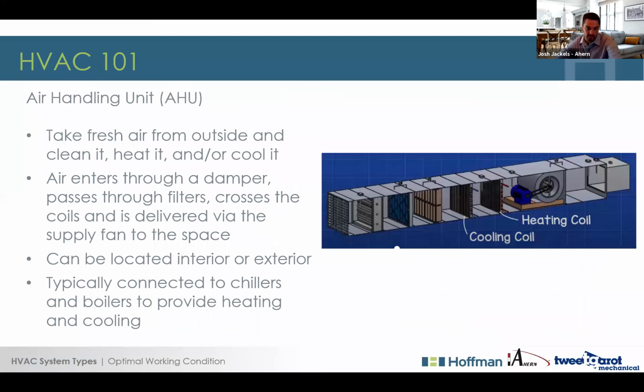Starting with a basic air handling unit, the basic functionality of the AHU system is to provide conditioned air to the facility. Fresh air enters the unit, passes through a damper, a series of filters, and crosses the coils, and is delivered via the supply fan to the space. As noted, there are a series of filters installed to ensure dust is collected, similar to the filter on your furnace at home. These systems are typically connected to chillers and boilers to provide heating and cooling. AHUs can be located inside a facility in a mechanical room or penthouse, or, like the RTU, they can also be placed outside.